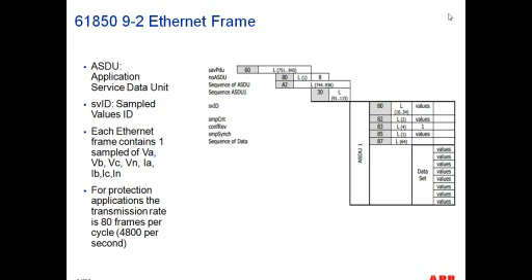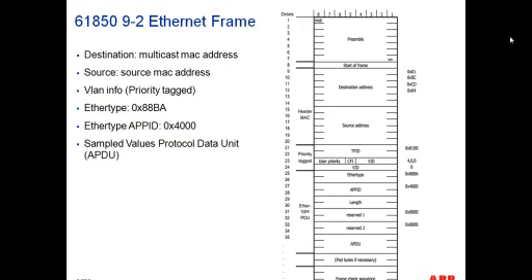Now let's take a look at our datagram, the Ethernet frame. Much of the information on this slide is standard for an Ethernet frame from any protocol, whether it's DNP, Modbus, or ICMP, for example. You have a preamble and a destination MAC address, which in the case of 9-2 or GOOSE messages is a multicast address. That means if VLANs are not used, this message will be relayed to all the ports on a switch, to put it in very basic terms.